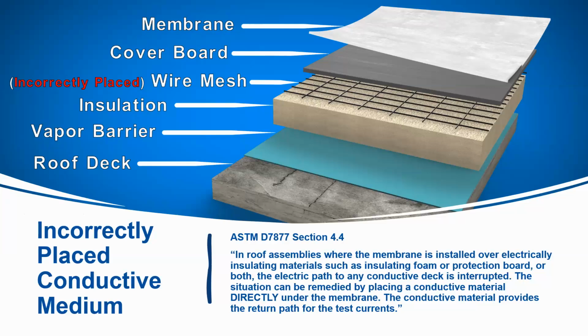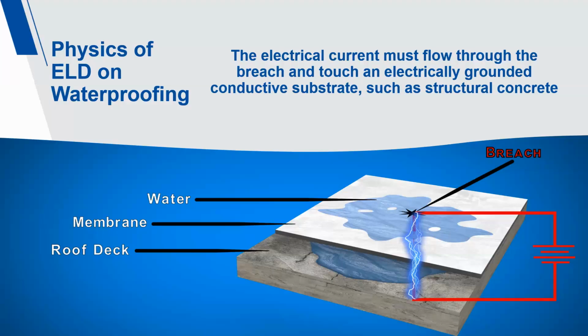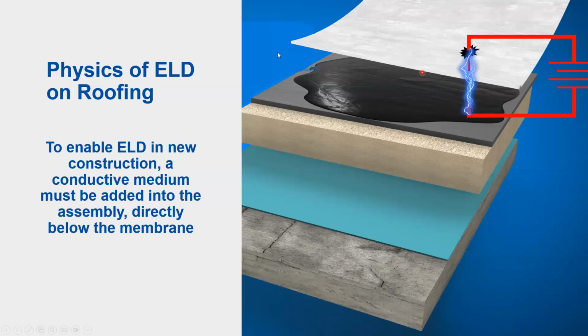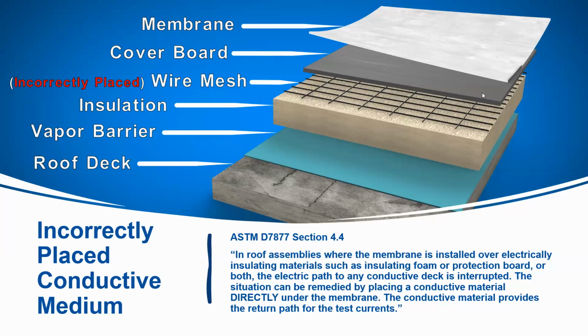So for the physics of ELD, if you've got a conductive substrate directly below the membrane, it's only a path from the top down. In this case, with the improperly placed conductive medium, this type of testing should not even be sold. Not only is it an invalid test, but it requires that moisture saturation and intrusion for the test to even work. It's not suggested.